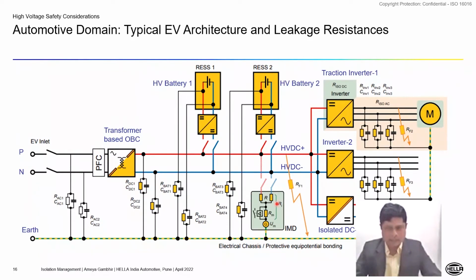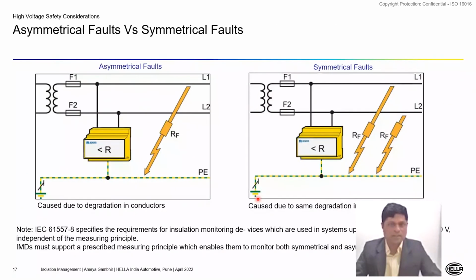And this shows a concept diagram of an IMD, which is sitting between chassis and the high voltage systems here. We'll be discussing more on this in the next slide. Before that, let's also discuss the asymmetrical and symmetrical faults. This shows a diagram where the two high voltage lines and then protective earth is connected through an IMD. Whenever there is a fault between one of the lines to earth, we call it an asymmetrical fault. Whenever there is a fault between both the lines to earth, and if the fault resistance is also the same, that is called a symmetrical fault.